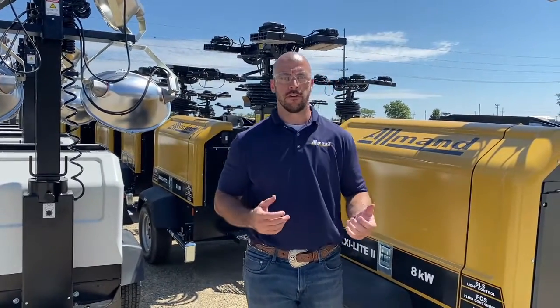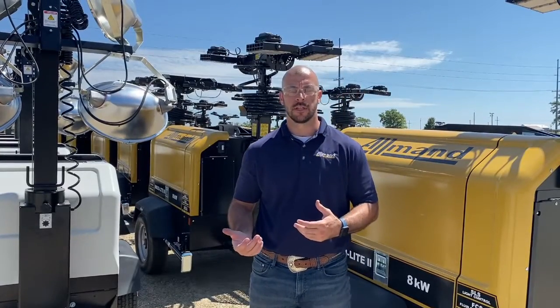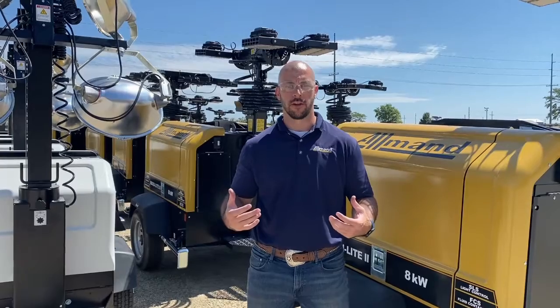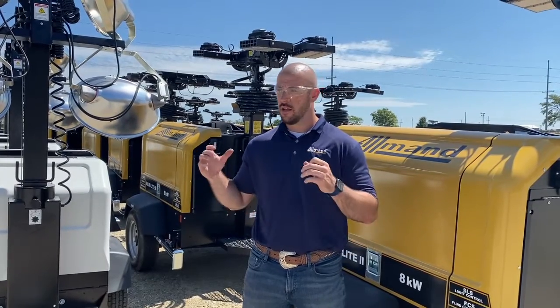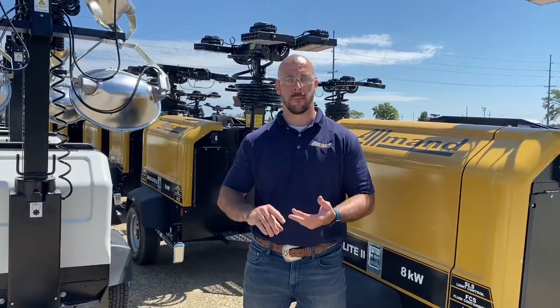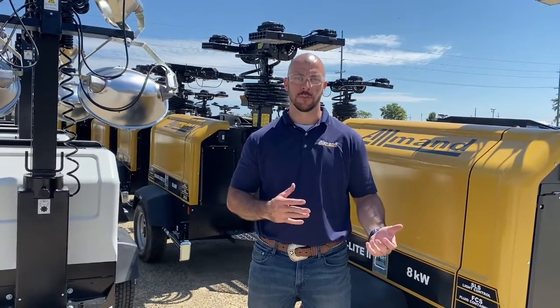We get a lot of questions in our training and technical service department about troubleshooting our Allmand light towers. One of the key things we use on all of our light towers is what we call our SLS system — that's Sequential Lighting System. What this does is protect your equipment — the generator, the ballast, the capacitors, everything that makes up our lighting circuit — from inadvertent startups or shutdowns.